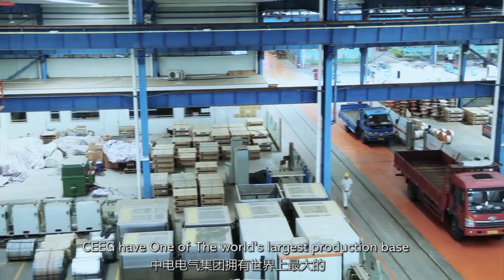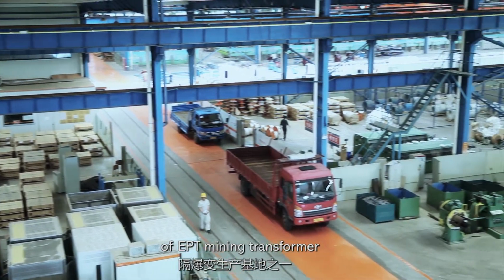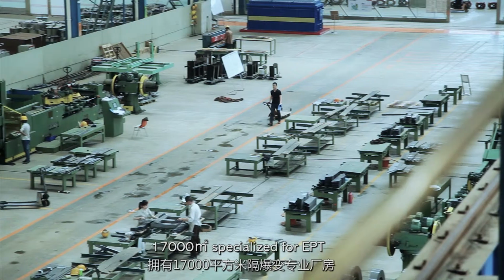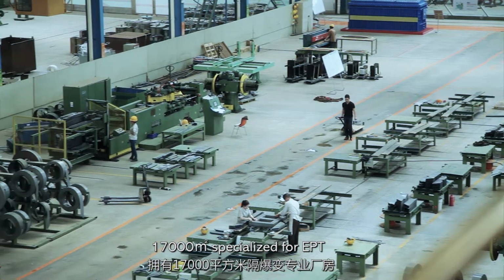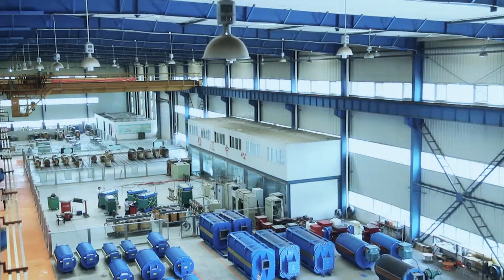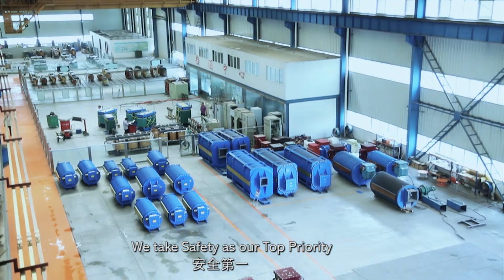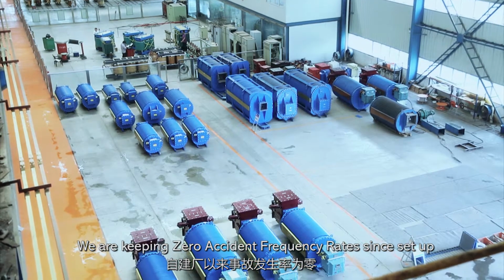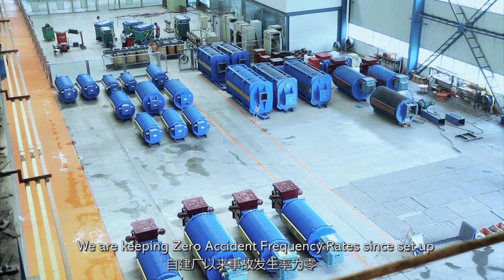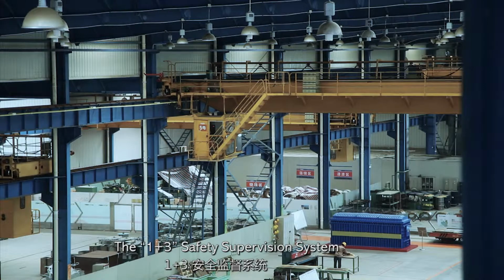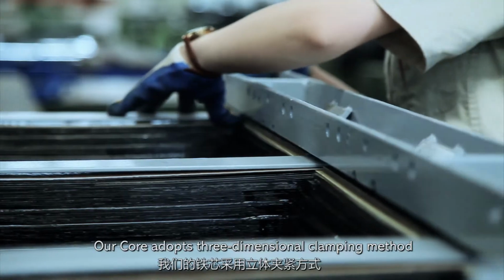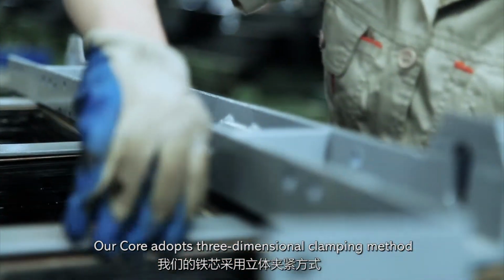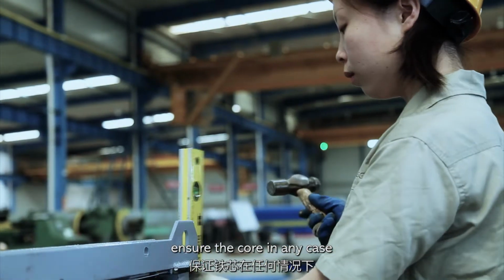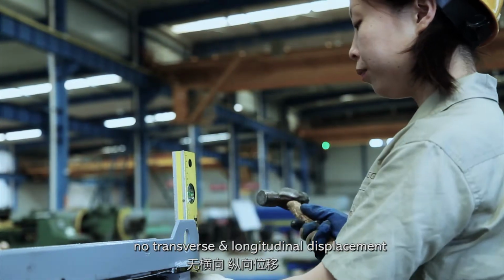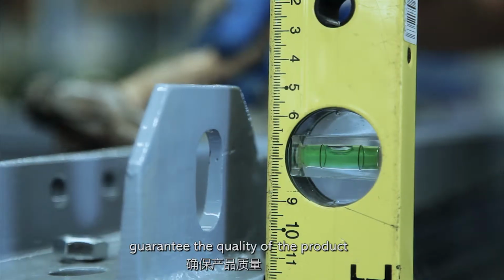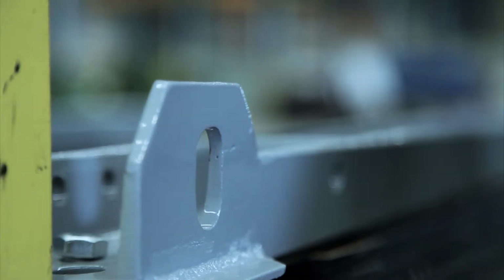CEEG has one of the world's largest production bases of EPT mining transformers, with 17,000 square meters specialized for EPT. We take safety as our top priority. We have kept a zero accident frequency rate since setup. The 1+3 Safety Supervision System. Our core adopts a 3-dimensional clamping method to ensure the core has no transverse or longitudinal displacement in any case, guaranteeing the quality of the product.